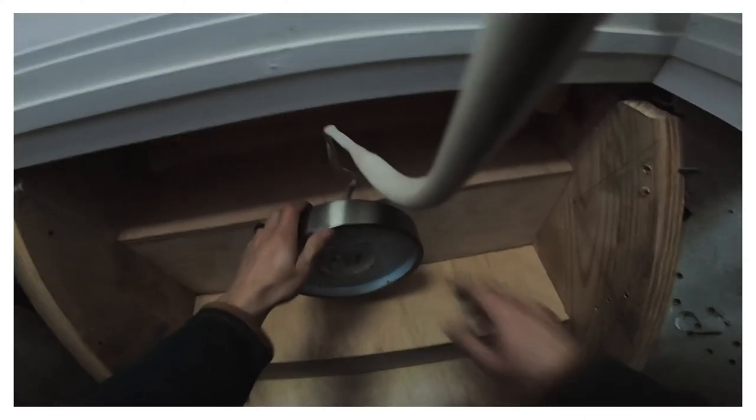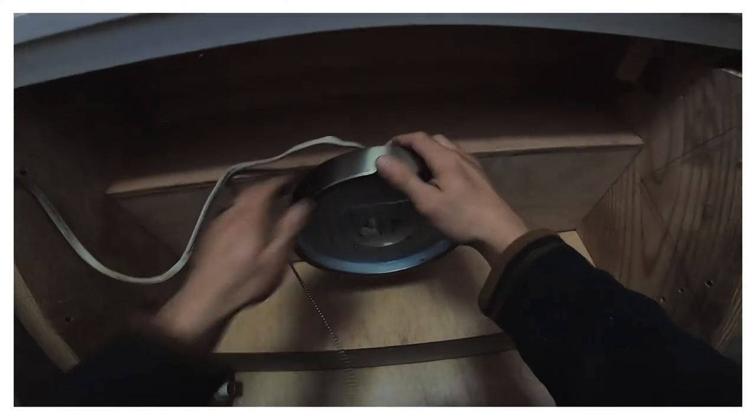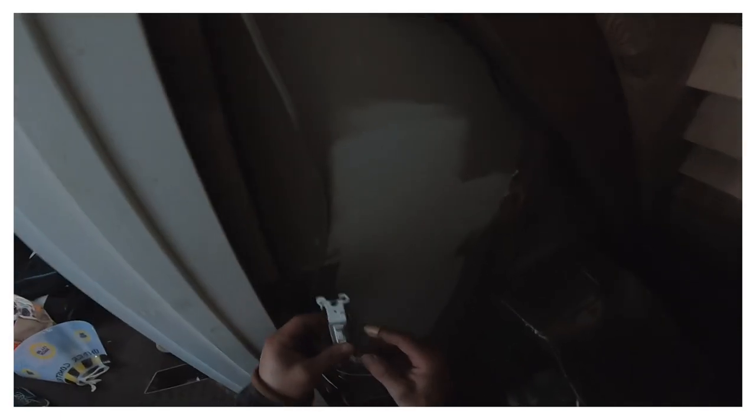All right, nice and secure. We are ready to put on this switch. Same thing, we'll cut a couple inches. Okay, here's the switch, pretty simple. You got three screws: green one is ground, and then the bottom is the hot coming in, top is the hot going out to the light.